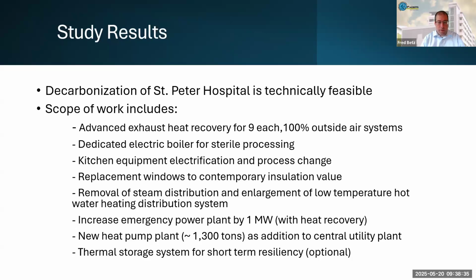Replacing the windows, we talked about envelope. The phasing of the steam distribution system, we did include that at length inside the case study. This is really a case-by-case basis, so hopefully it gives you some ideas, but each steam distribution system is unique and brings its own challenges. As part of this plan, we're adding about 1 megawatt of generators to support the heat pumps for the wintertime load, because right now the boilers are on fuel oil for the winter for emergency operation, so we need to have something similar.